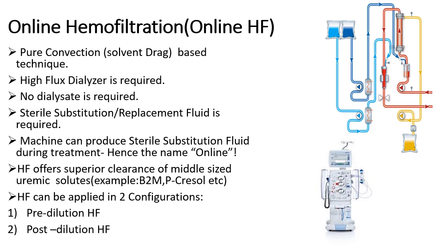For performing haemofiltration, you need a high flux dialyzer with very high water permeability. No dialysate is required because there is no diffusion. In order to compensate the fluid loss, you replace the fluid volume with an electrolyte solution known as substitution fluid or replacement fluid. The procedure is called online HF because the dialysis machine itself can produce the sterile substitution fluid required for treatment.